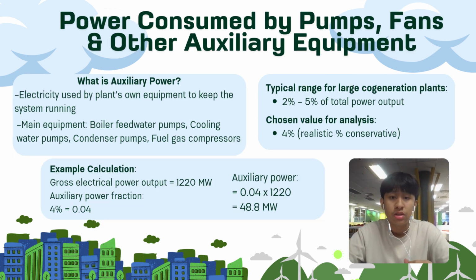So, for power consumed by pumps, fans, and other auxiliary equipment, let me get to the details. What is auxiliary power? It is electricity used by the plant's own equipment to keep the system running. The main equipment for the auxiliary power is boiler, feed water pumps, cooling water pumps, condenser pumps, and fuel gas compressors. The typical range for a large cogeneration plant is 2% to 5% of total power output. So the chosen value for analysis is 4%, which is realistic and conservative.